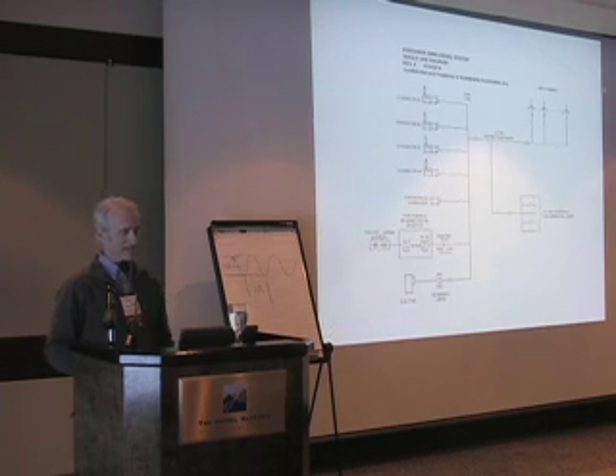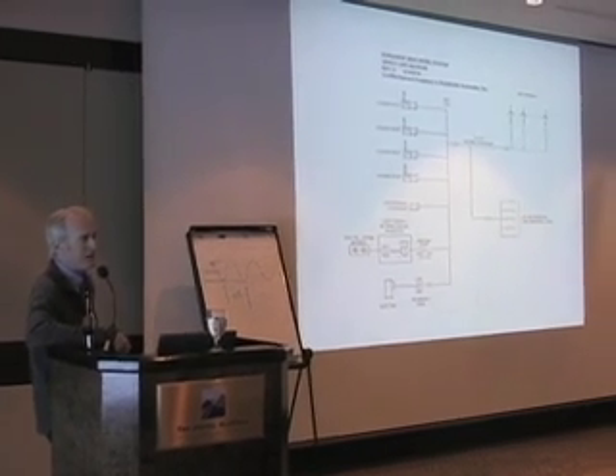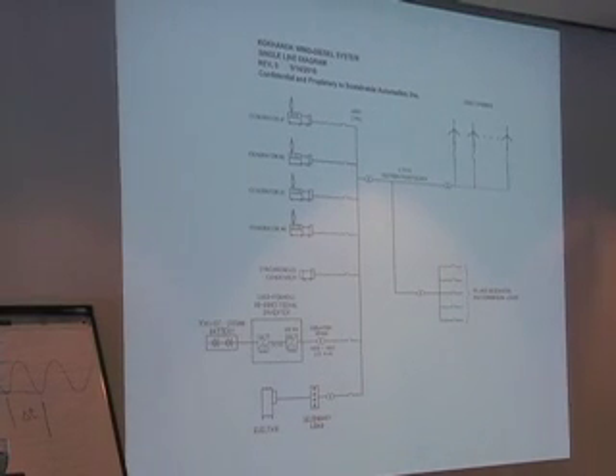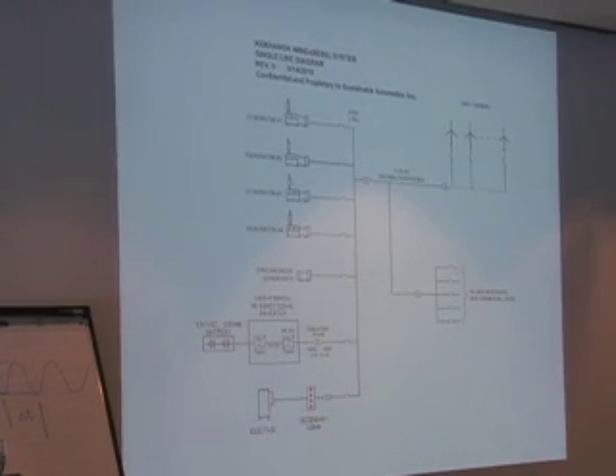I'm going to just switch to, if you can see that, the one-line diagram for the power system at Kokhanok, which some of you may be visiting on Saturday. It's an existing diesel power plant consisting of 4 generators, a synchronous condenser, a secondary load controller, and a battery inverter system. And then out on the grid, I've shown more here, but there are actually two 95 kilowatt wind turbines, and then you've got the village load. So which of these things are part of the problem? In other words, they don't help you control frequency and voltage, and which do?